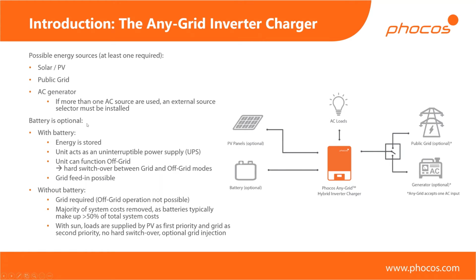Then, as mentioned, the battery is optional. So you don't necessarily need to have one. If you do connect a battery, then of course you use that as storage. The device can automatically act as an uninterruptible power supply, simply because it switches over so quickly between grid mode and off-grid mode. And in fact, when you're working between those two modes, when you're in off-grid mode, let's say your priority is to use as much PV energy as you can. So you want to voluntarily disconnect from the grid when you don't need it. Well, in that case, you will literally be disconnected from the grid. Both line and neutral will be disconnected from the grid, so there's no risk of backfeeding into the grid.